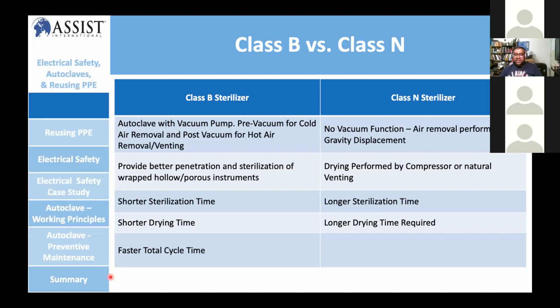And class N sterilization has no vacuum function. Air removal is performed by gravity displacement, and drying is performed by compression or natural venting by the pressure itself. It requires long sterilization time and long drying time. So this is the difference between class B and class N.